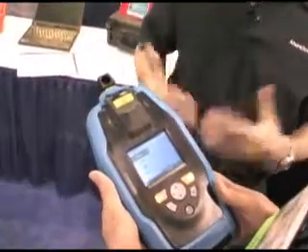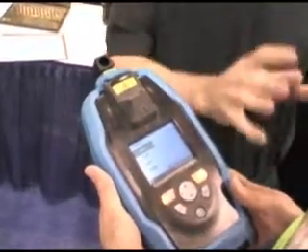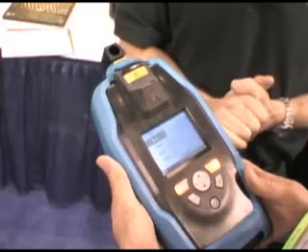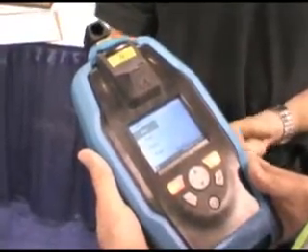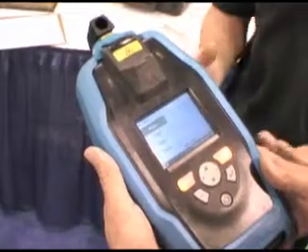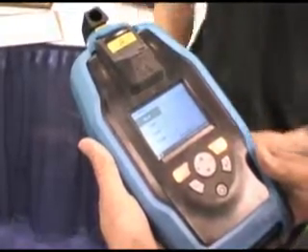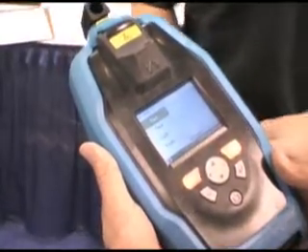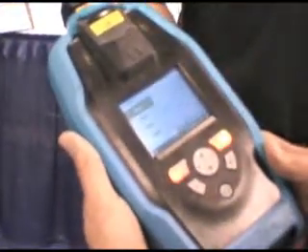The premise is we've logged into the instrument. It is a 21 CFR Part 11 compliant instrument. I've logged in with a password, which provides the level of access and control you have, but also ensures that you are trained — this is a laser-based device, a Class 3B laser, and we don't want people to do silly things with it. We have three different modes of inspection: we can put on a nose cone and go through the bag, we have a vial holder, and we have the ability to go down into a drum. Let's put a vial in there.